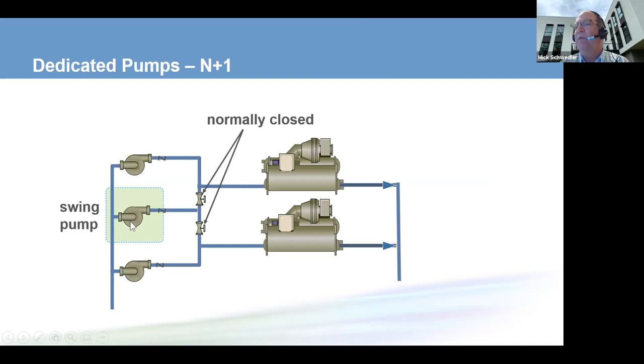And then we have a swing pump. And with valves, this swing pump could work either with this top chiller or with this bottom chiller. And we could change which chiller it's working with by opening or closing particular valves. So this is where you have N plus one pumps, but you don't have to have double the number of pumps.